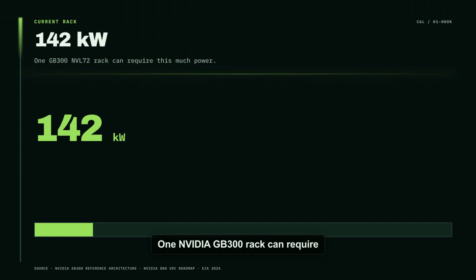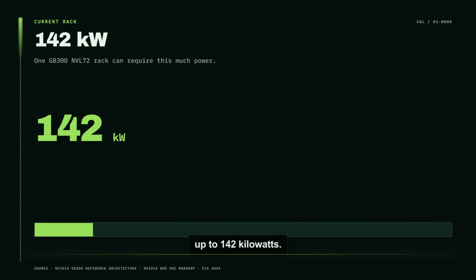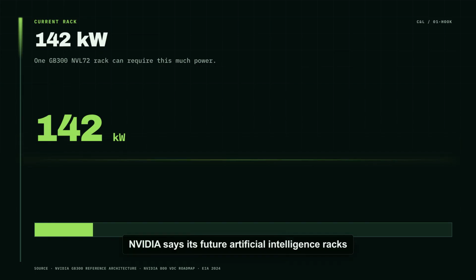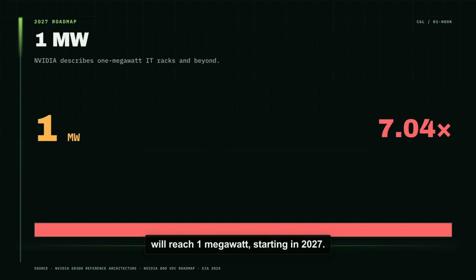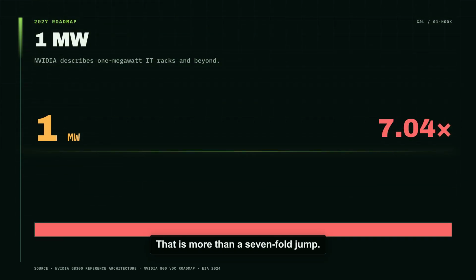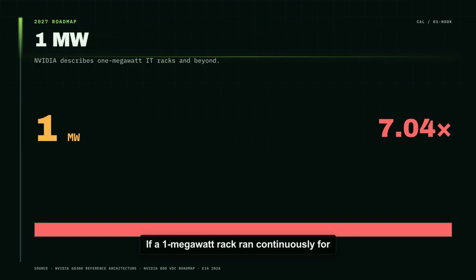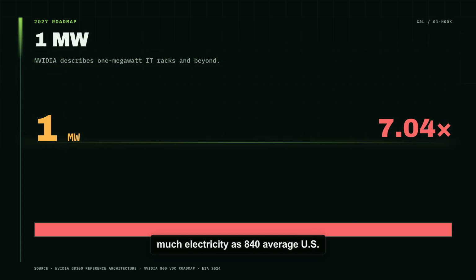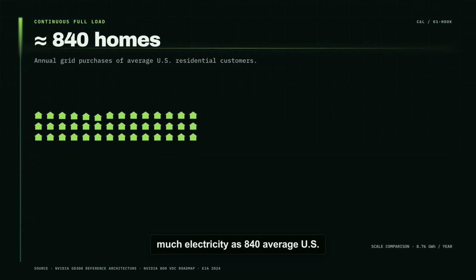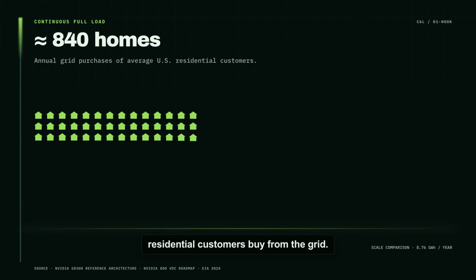One NVIDIA GB300 rack can require up to 142 kilowatts. NVIDIA says its future artificial intelligence racks will reach 1 megawatt, starting in 2027. That is more than a 7-fold jump. If a 1 megawatt rack ran continuously for a year, it would use about as much electricity as 840 average U.S. residential customers buy from the grid.